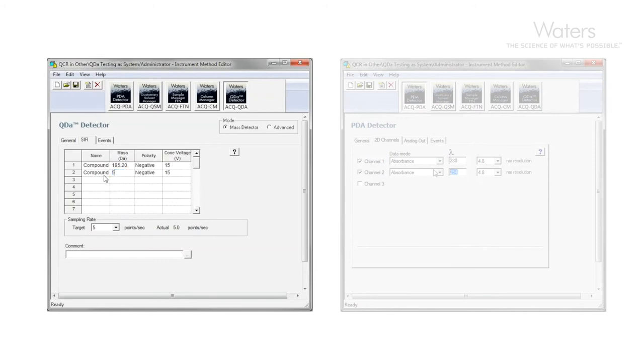Single ion recording enables targeted analysis of a set of analytes, which means we have greater selectivity, increased sensitivity, and increased confidence in the results of your analysis. You can quantify analytes or components that may co-elute or cannot be seen with optical detectors. This means you can have shorter run times because baseline resolution is not needed. Ultimately, you benefit from higher throughput and increased productivity.